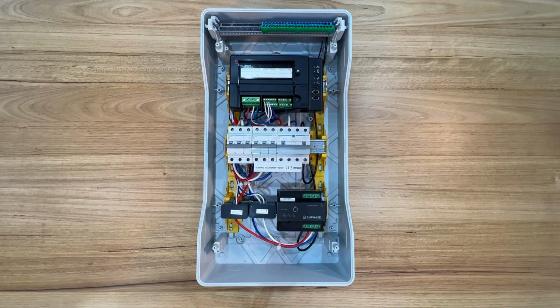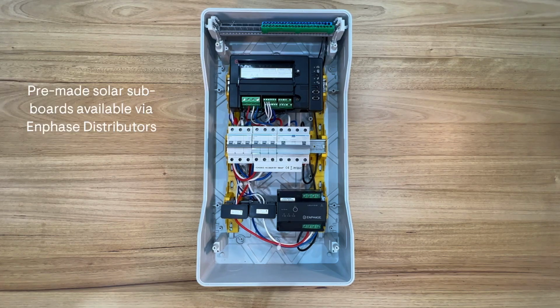Now this is a nice working example of how you can complete your configuration for a multi-phase site. So to help your installation, you can see here we're using a 36 pole enclosure which allows enough space to put 3 200 amp CTs for solar production within the same board, and you'll notice that the IQ gateway and the circuit breakers all fit well within this space. Now the example I'm showing you is a manufacturer pre-made solar subboard. You'll be able to source these from your solar supplier, so ask them for further details.